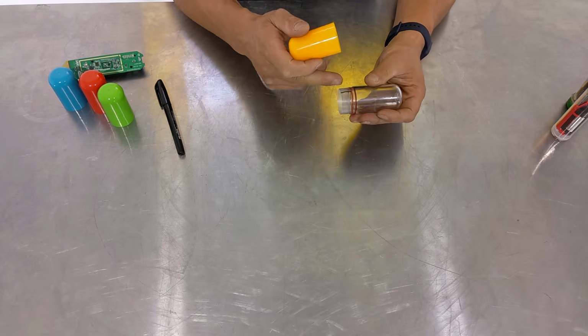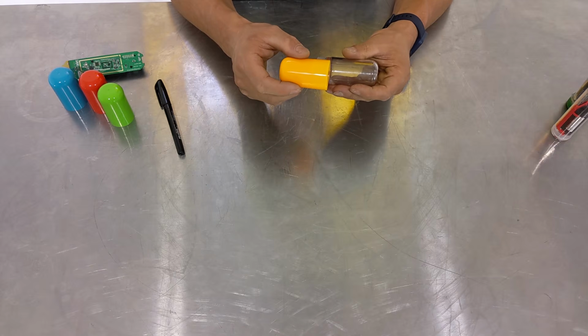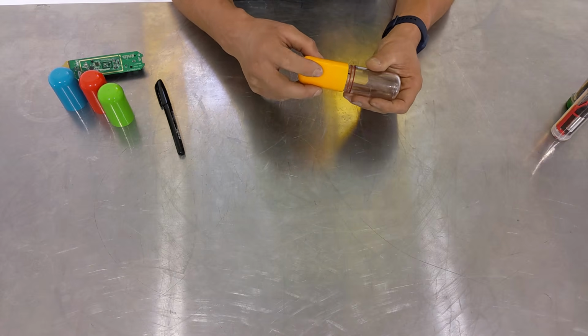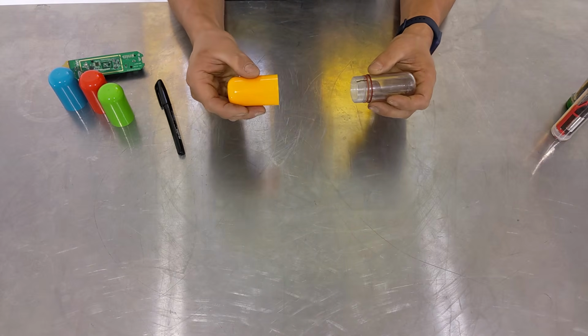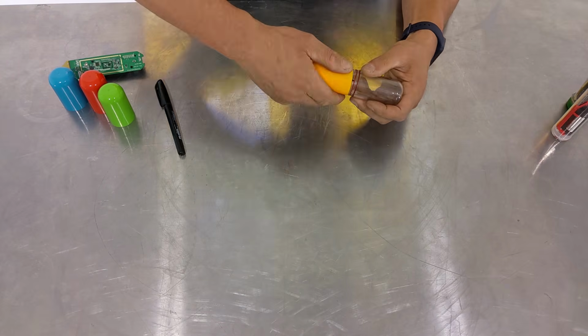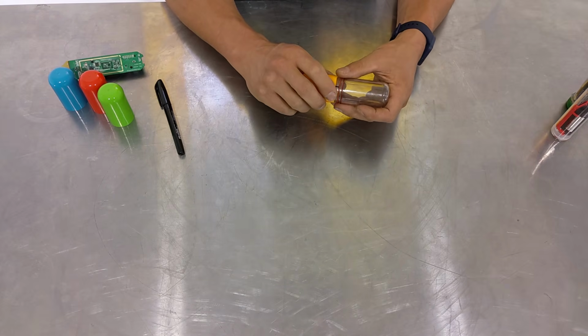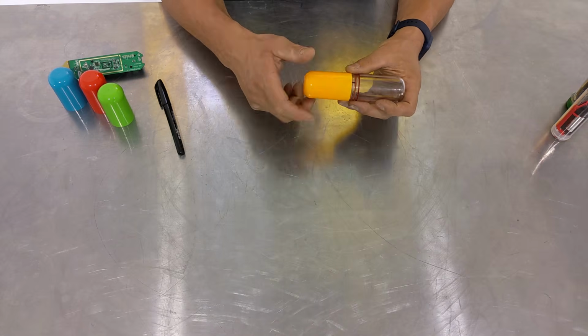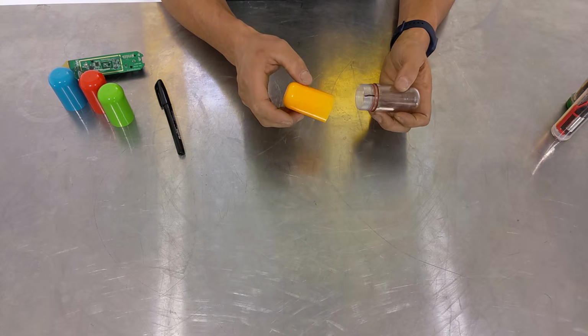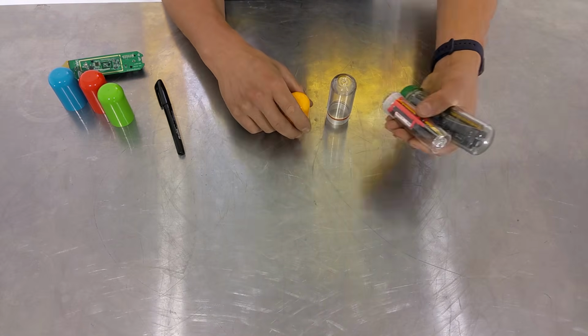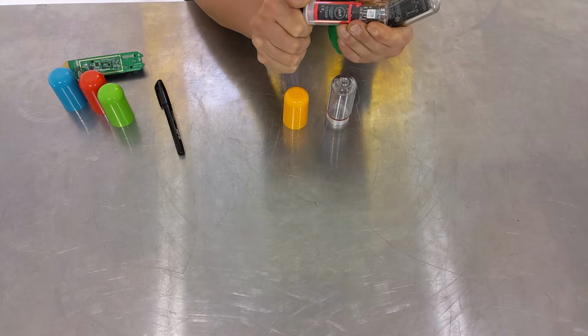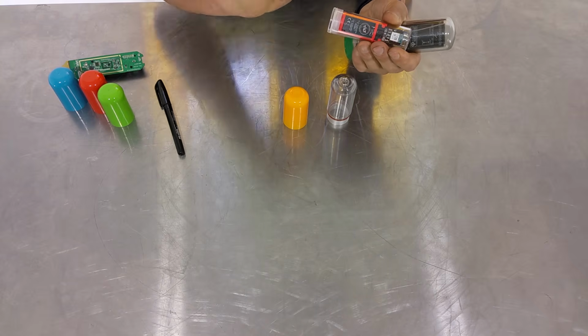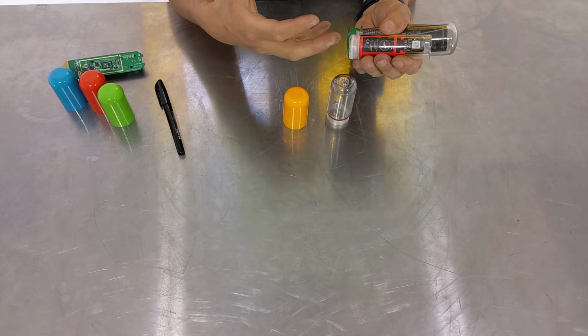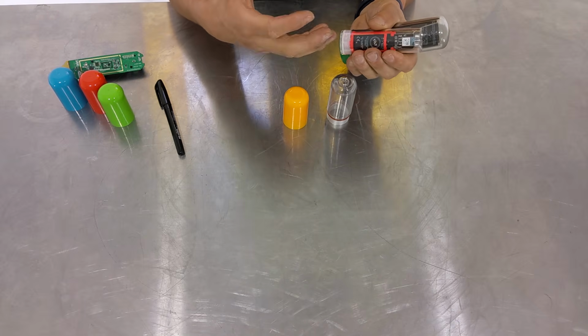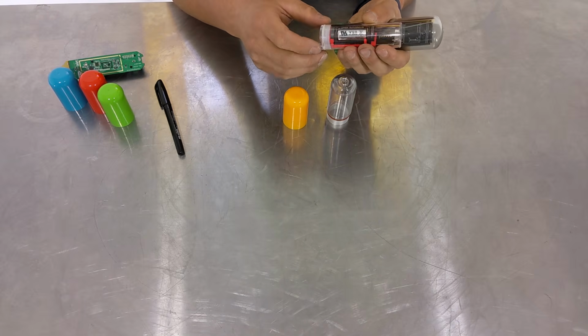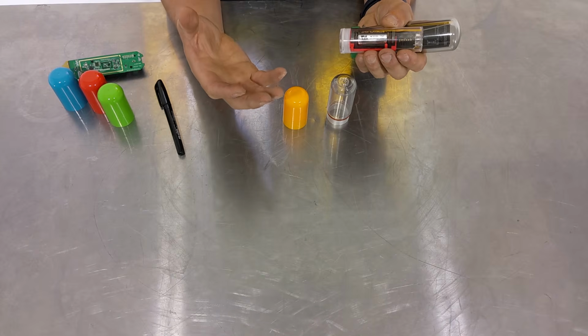Now, with these types of O-rings, it doesn't really matter if it's extremely tight or a little bit less tight because they're radial sealing O-rings, not a face seal. So it doesn't rely on this being incredibly tight, done up against the other part of the housing in order for the seal to get sufficient compression. So you really don't have to do it up tight. But when we were testing all of these devices, we did notice that when you do up the cap slightly tight or very tight, that can affect the gravity reading and give you a little bit of an inaccurate reading if it's not done up consistently, which is the main problem.